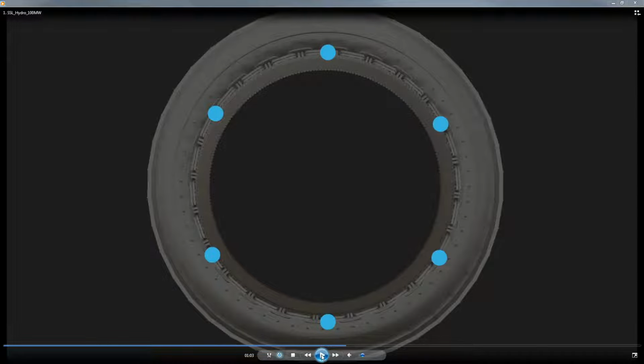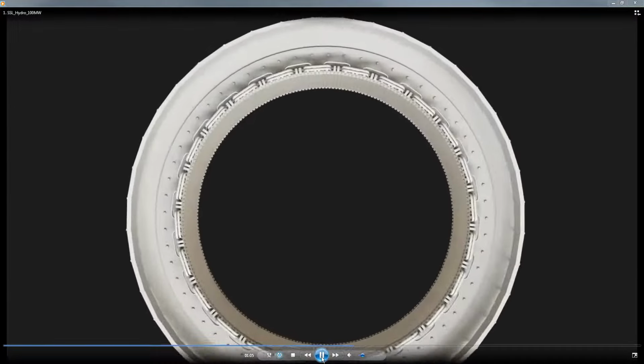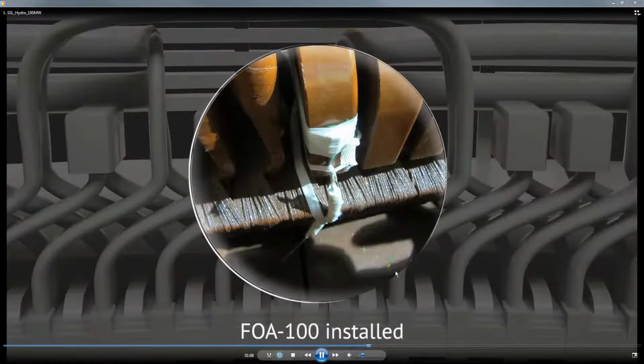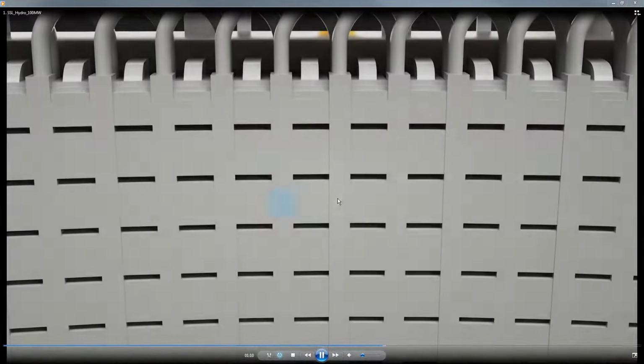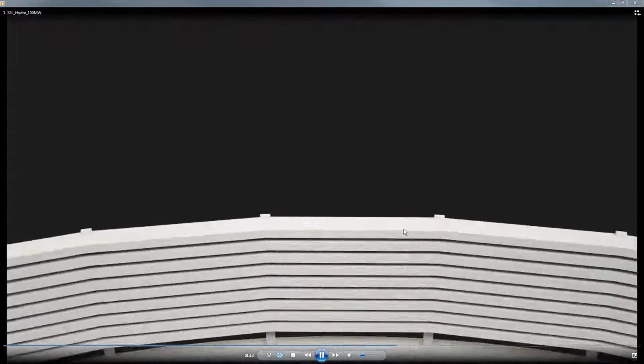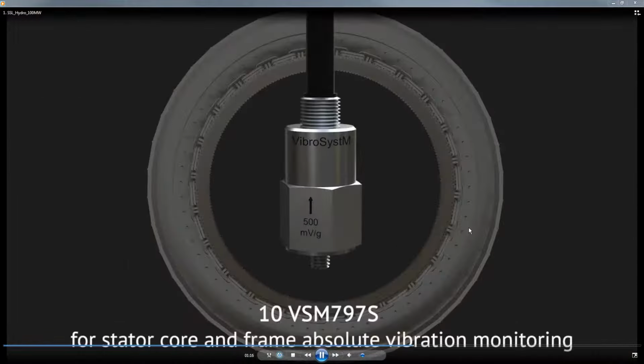These are capacitive probes. They're installed on the wedges, looking towards the stator bar to see how tight the wedging system is, how tight the bars are in the slots, because as you know, epoxy mica hates to rub against anything, and it creates wear and tear of the insulation, so you want the vibration to be as little as possible. So those types of sensors are able to monitor that and tell you if there's an issue. So you have an FOA, which is installed on the cap, and you'll have a stator bar vibration sensor looking at the bar inside the slot.